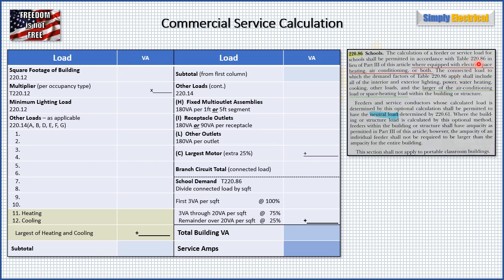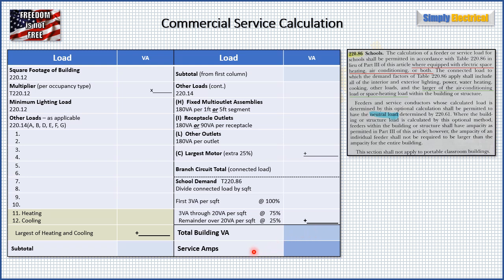That connected load is what we apply to Table 220.86. I've made a simple table for this. We start with the square footage of the building and get our multiplier to find our minimum lighting load. Then we take all our loads, add them up to get our connected load. After that, we plug it into Table 220.86 to find our total demand for the school. Once we have that total building VA, we divide by our voltage and that gives us our service size in amps.